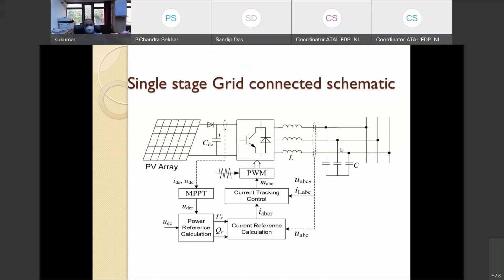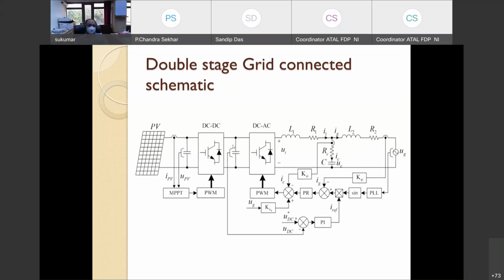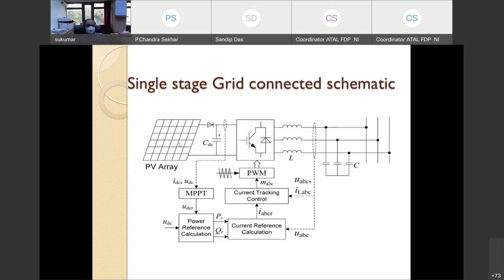This same philosophy can also be extended to single stage. However, there will be a small difference here. In the double stage, the DC voltage is generally constant, whereas in a single stage, it varies with respect to the MPPT algorithm. And when it varies with respect to the MPPT algorithm, then the stability and the operation of the inverter becomes a little bit challenging.